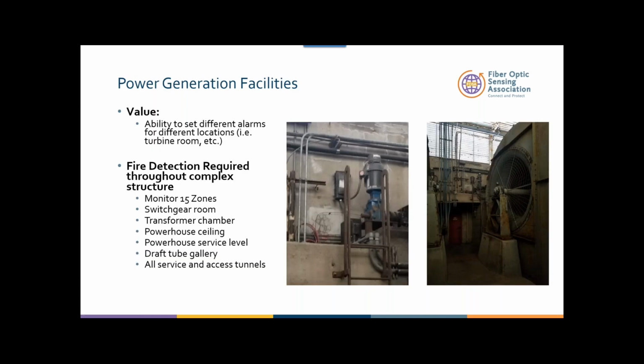Power generation facilities. You have facilities where you have different temperatures within different rooms. The ability to change and to be versatile enough to monitor up to, let's say, 15 zones or 1,000 zones. You can have switch gears. This is an application where we did 15 zones. You have switch gear rooms, we have transformer chambers, powerhouse ceilings, powerhouse service levels, draft tube gallery, we have so many different assets that can be monitored at the same time, different rooms that can be monitored. And you just run one single cable.